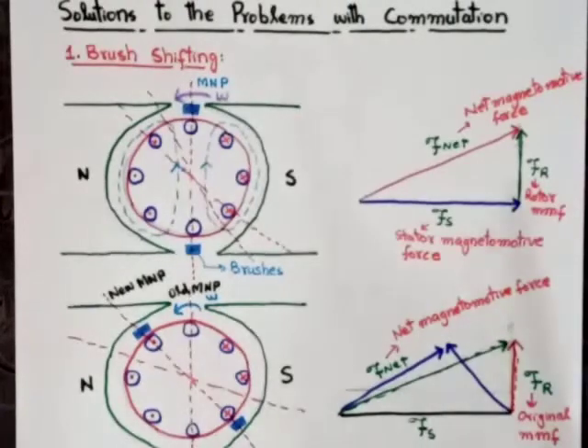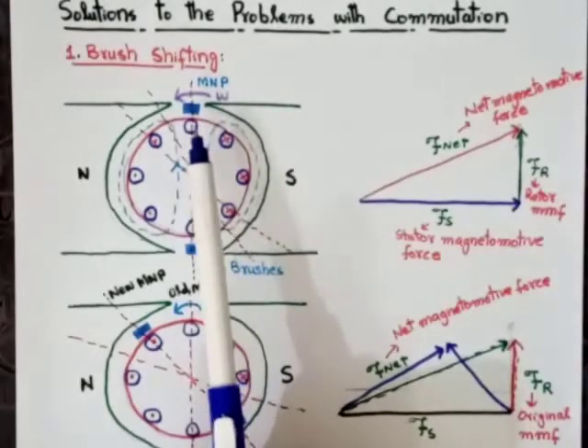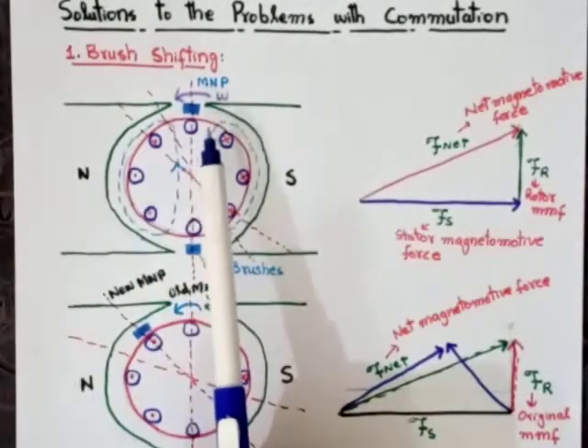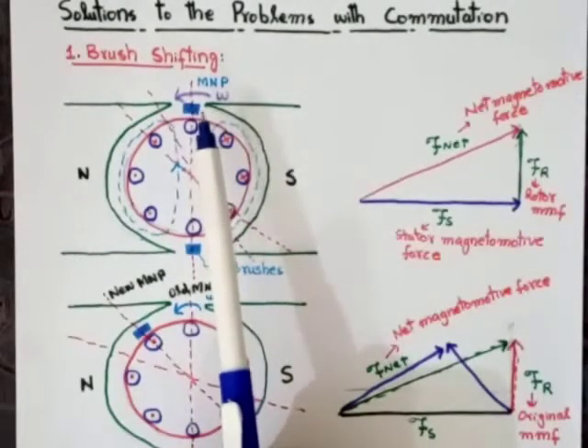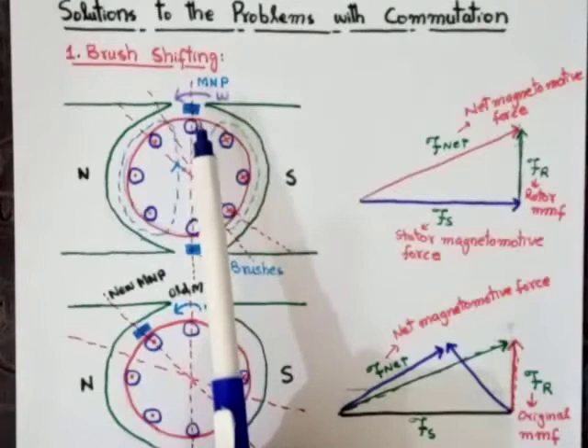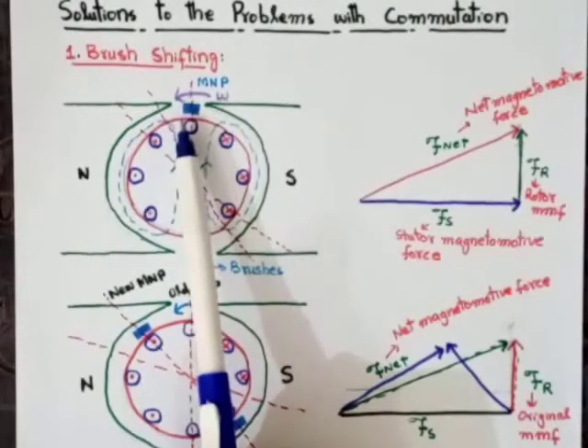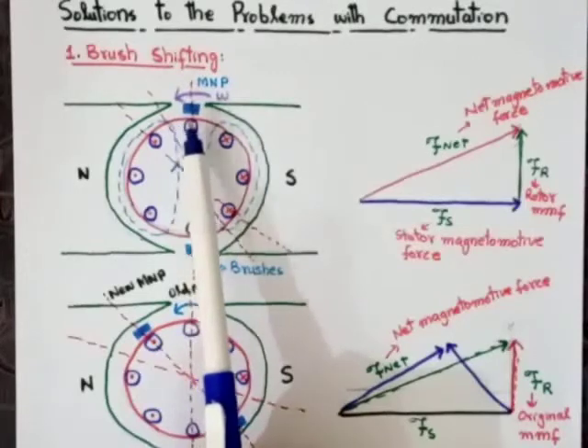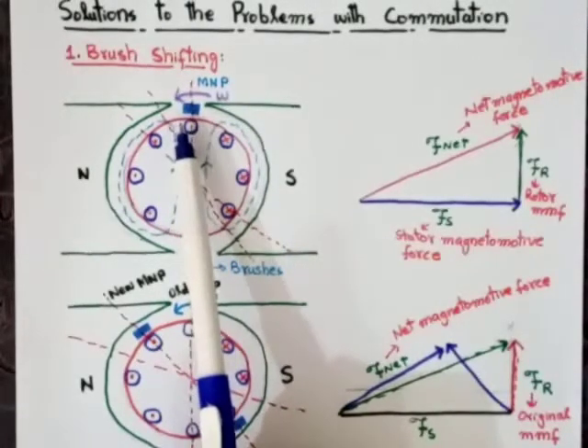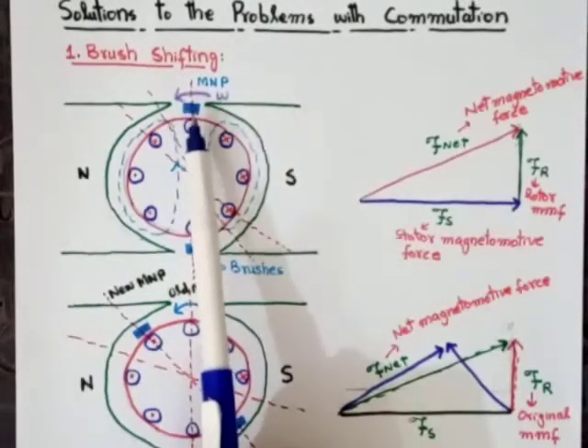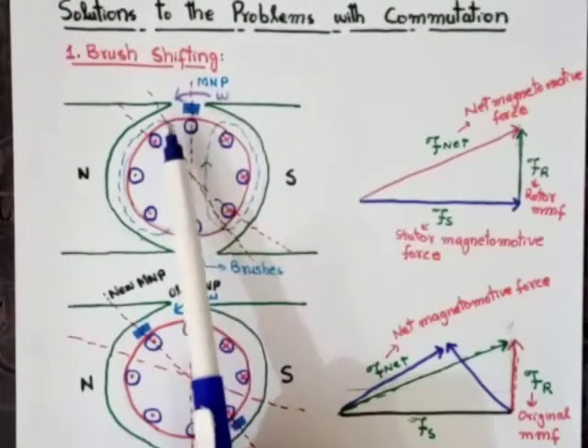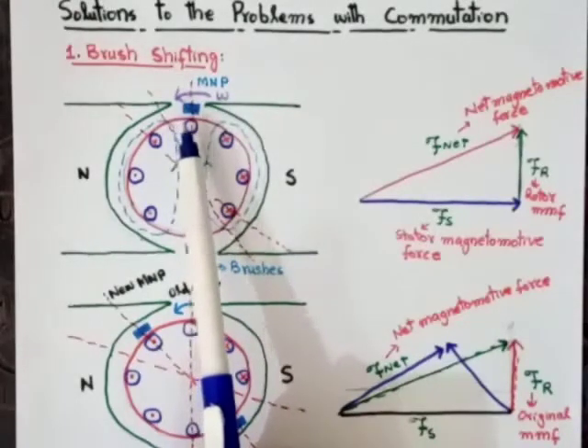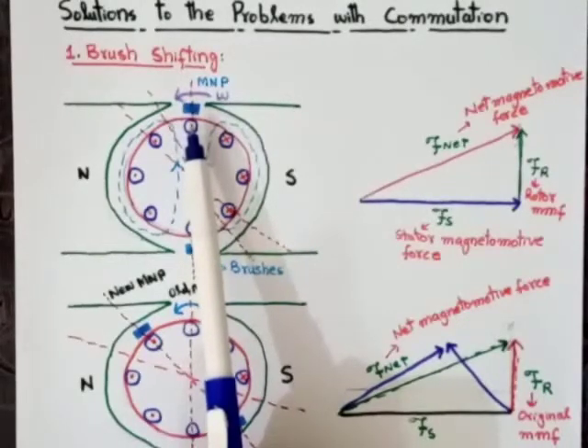As we know, the magnetic neutral plane is shifted in the direction of rotation in the case of a generator, and in the opposite direction in the case of a motor. If we shift the brush manually in the direction of the magnetic neutral plane, then the problem of sparking can be completely or partially reduced. We want to shift the brushes in the direction of the magnetic neutral plane, and by doing this we can reduce the problem of sparking across the brushes.